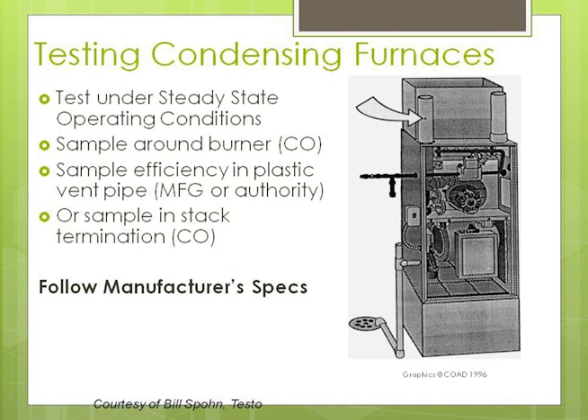Condensing furnaces have the PVC pipe. They say to drill a hole in the PVC pipe to test them, but people would get really mad if you did that. So if you test them at all, you test them at the outlet outside the house to make sure that the carbon monoxide there is less than 25 parts per million.